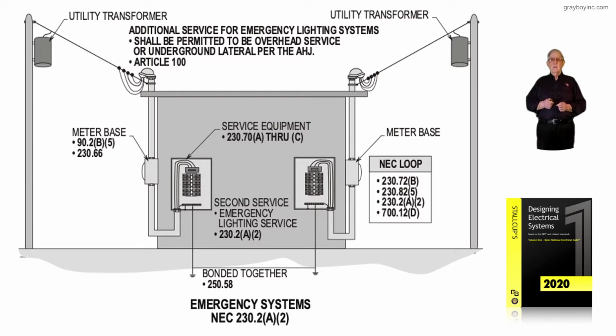Notice 230.72(B) would deal with the number of disconnects that are allowed. You know, we can have up to six grouped in any one location. 230.82(5), again, that item 5 would allow even a tap ahead of the main where the authority having jurisdiction would permit it.